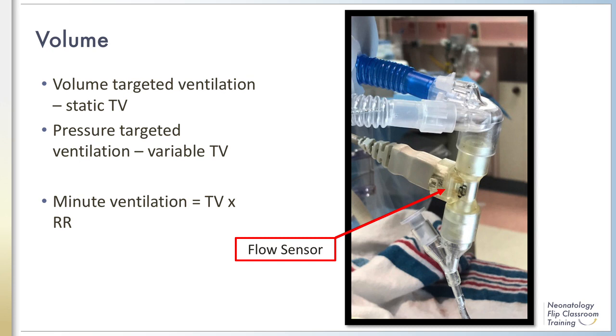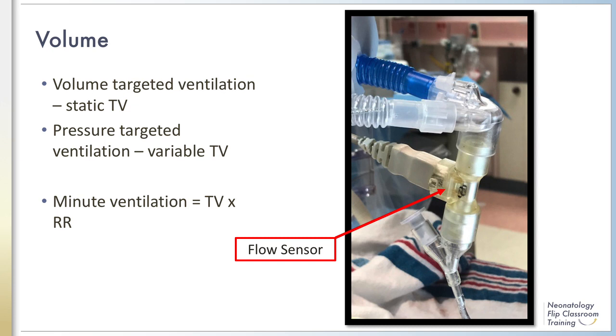Minute ventilation can also be calculated by multiplying the respiratory rate by the average tidal volume. The flow sensor is usually located between the endotracheal tube and the ventilator tubing on neonatal ventilators.